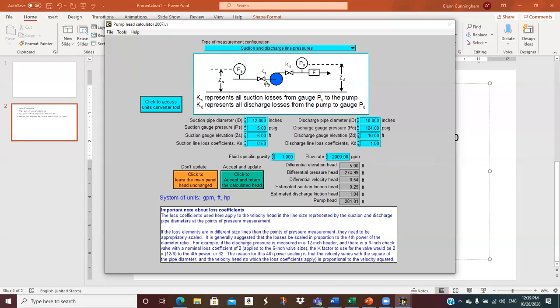Differential velocity head. Well, the kinetic energy is greater in the discharge pipe than the suction pipe because the diameter is smaller. So that's V squared over 2G. You can calculate V squared over 2G if you want to, but why bother when this will do it for you, other than on your homework. Estimated suction friction head loss, 0.25 feet. That's from that suction line loss coefficient of 0.5. So that's V squared over 2G on the suction side times 0.5. And the discharge line loss on the discharge side is 1.04. I add all those up, and that's your pump head.